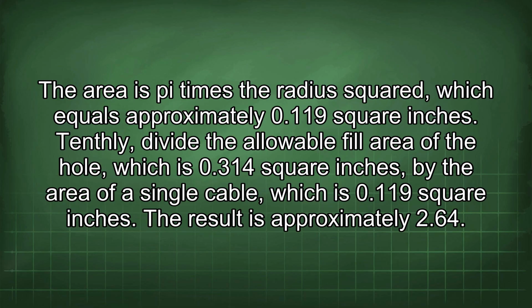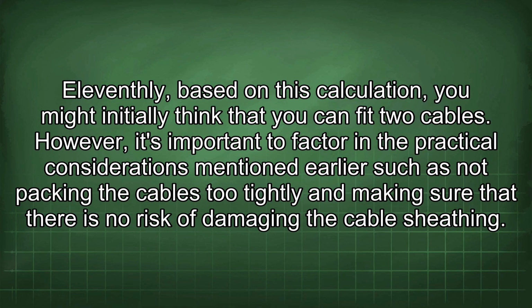Tenthly, divide the allowable fill area of the hole, which is 0.314 square inches, by the area of a single cable, which is 0.119 square inches. The result is approximately 2.64. 11thly, based on this calculation, you might initially think that you could fit 2 cables. However, it's important to factor in the practical considerations mentioned earlier, such as not packing the cables too tightly and making sure that there is no risk of damaging the cable sheathing.